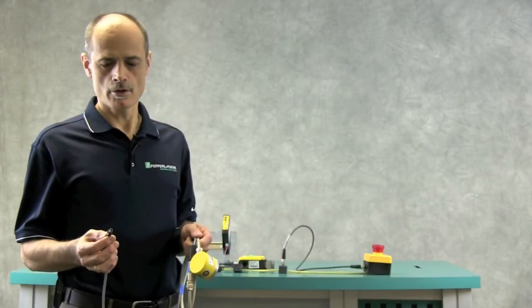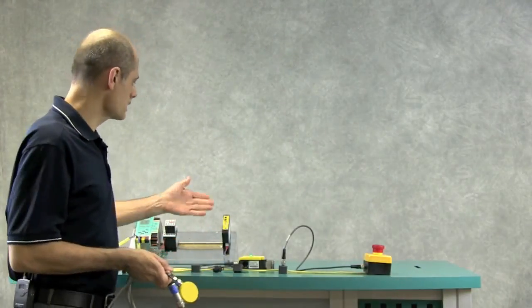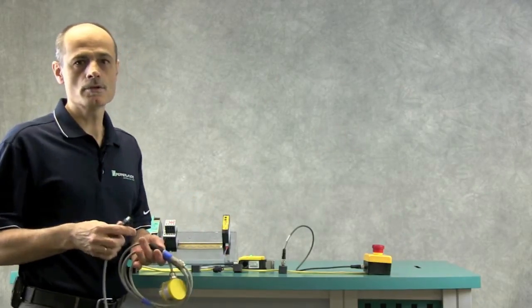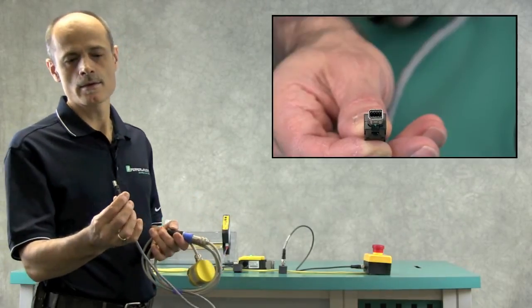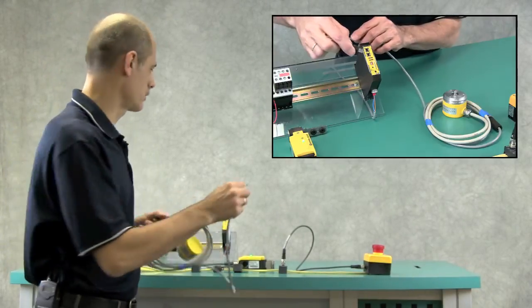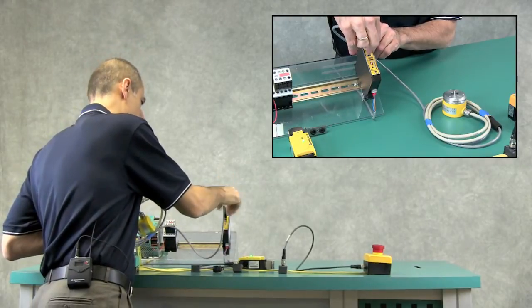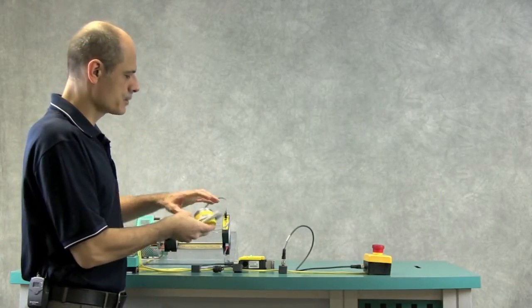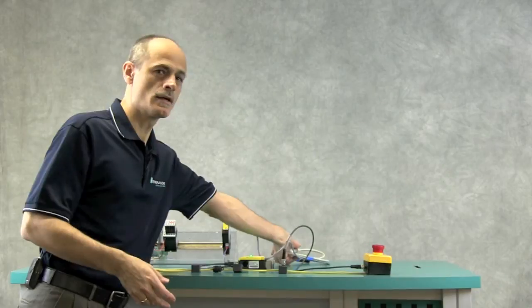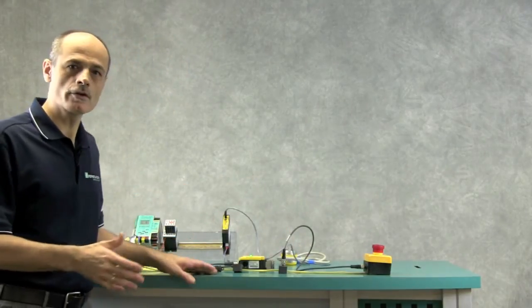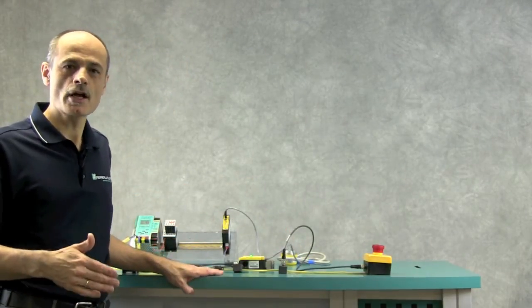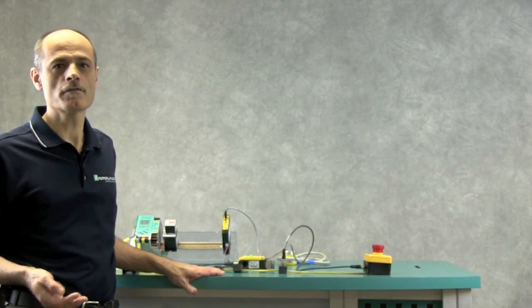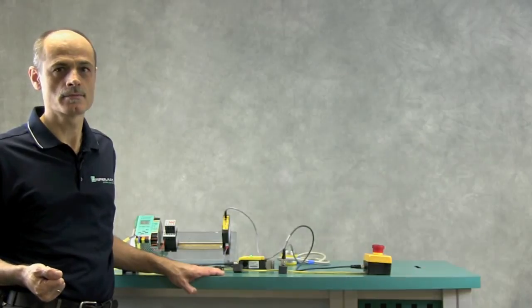The safety encoder will be connected to this AS interface module using a mini I.O. connector. This module enables two encoders to be connected and is going to be configured to check for safe speed, safe off, and direction of rotation.